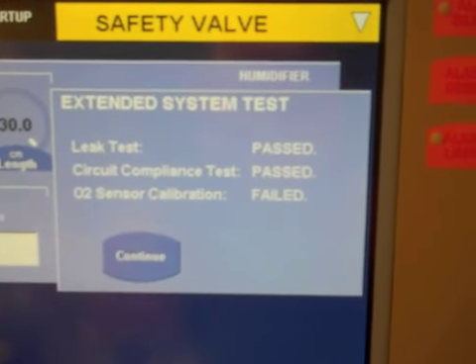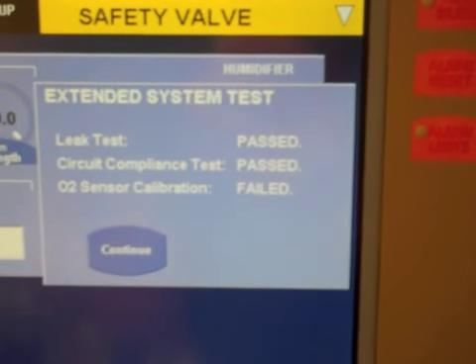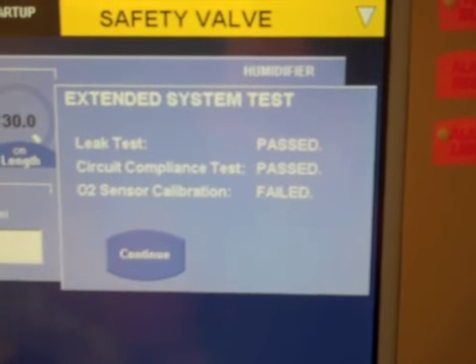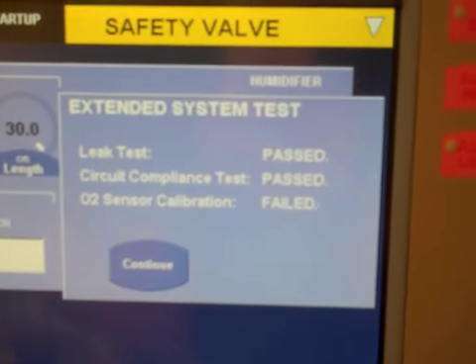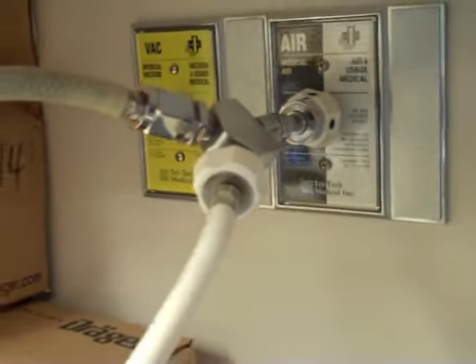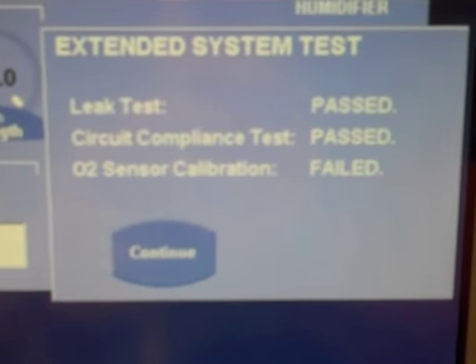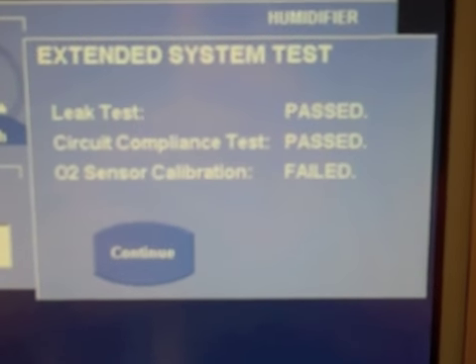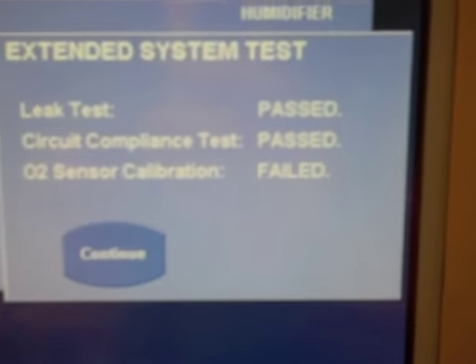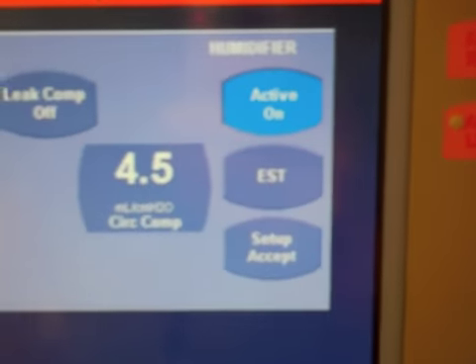Okay, so you can see that our leak test has passed, our circuit compliance test has passed, but we've got an O2 sensor calibration failure. The reason we have that is you guys have probably seen in our lab we just wire it off to a 50 psi air source. Make sure in the clinical setting, obviously, that's hooked up to 50 psi DISS O2. Okay, so for our purposes we're going to go ahead and continue here.